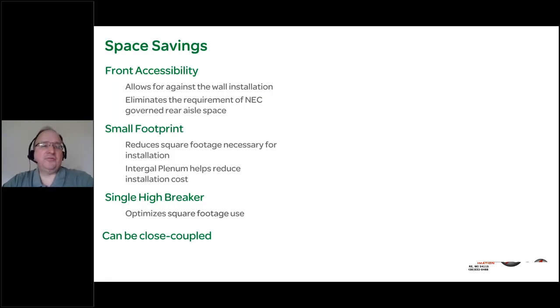In terms of space savings and front accessibility, this is something you obviously don't get with metal-clad switchgear. This allows for installation against a wall. It eliminates the National Electric Code requirement governing rear aisle space. So in terms of real estate savings, not only are we saving in the width dimension, but the fact that we can install against a wall saves a tremendous amount of space inside the electrical room. So we're reducing the square footage necessary for installation. And of course, when you optimize the square footage use, you're saving your customer money as well.